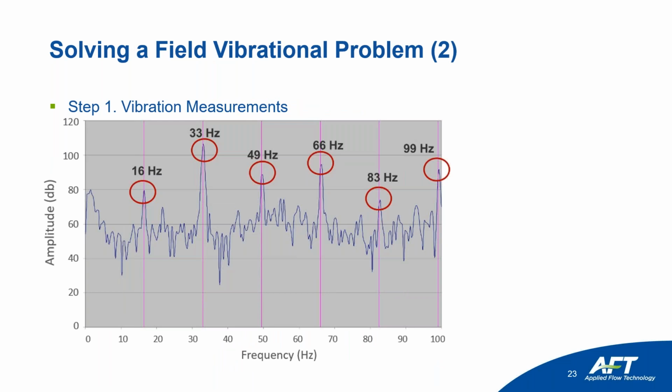So first step, we do vibration measurements in the field. We see that the predominant frequencies are 16 hertz, 33 hertz, 49 hertz, 66 hertz, 83 hertz, 99 hertz.